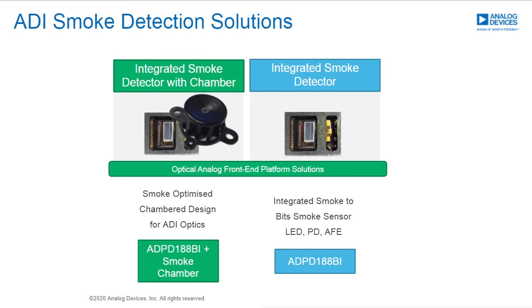This slide goes into the full smoke detection solution. So, for most smoke detectors on the market today, there's going to be some type of smoke chamber that encloses the optics to control the environment for airflow, for keeping insects out, for reducing ambient light into your optics. Because of the unique way that we measure the smoke, whereas we're measuring the smoke directly above the module rather than in some more forward scattering type method that shoots a beam at an angle across the top of a PCB and receives the signal into a photodiode, up to 5 to 10 centimeters away, we've had to design our own chamber to deal with the new challenges presented with the method that we use.